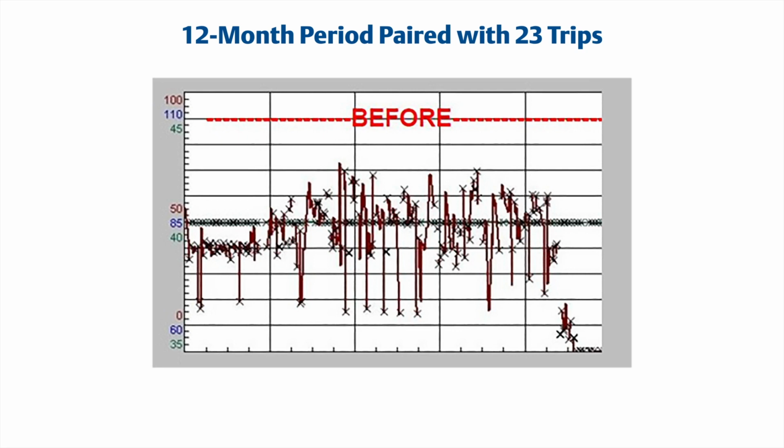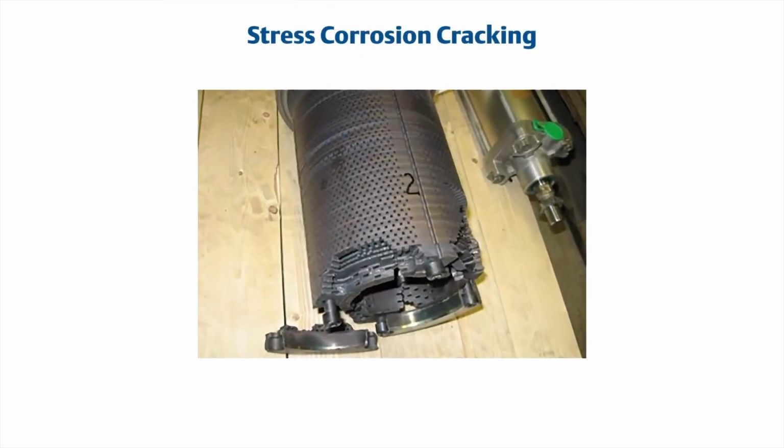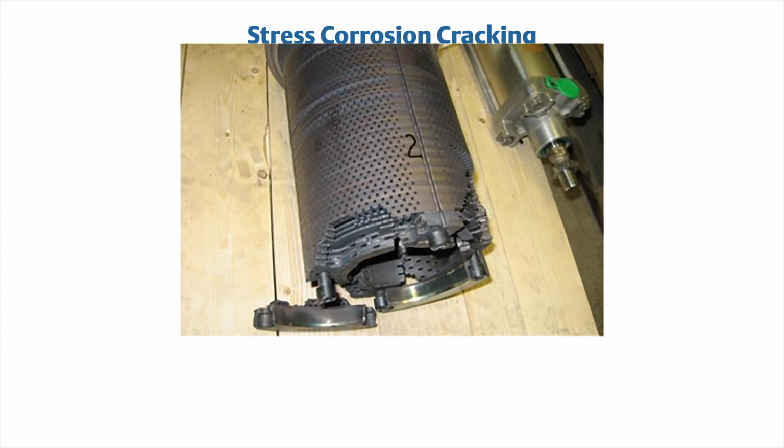What happens if you don't select the ideal control valve assembly? This first picture, you can see the set point, and you can watch the valve trying to operate at the same point, but it is jumping all over the place. Poor control can lead to wasted feedstock, as well as off-spec product. Also, if you don't consider all the metallurgical aspects that are going on inside that valve, you can have stress corrosion cracking and trim failures that are unexpected.